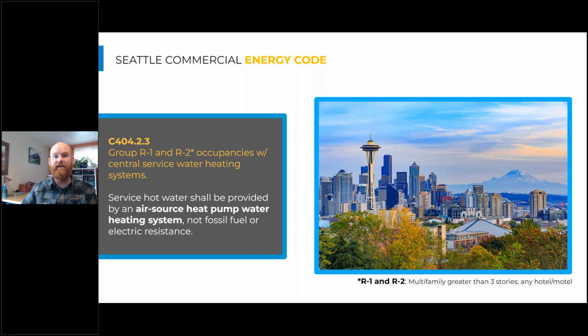Now, it also makes sense in most, if not all, commercial building types: libraries, fire stations, office buildings, restaurants, commercial kitchens. We're still going to see a significant reduction in the annual energy usage when we implement a heat pump water heater. But in multifamily and hotel motel, we take showers, and so there's typically a large hot water demand, and so there's a lot of savings there. And that's one reason that the Energy Code is currently prioritizing making sure that building stock is built with these high efficient heat pump water heating systems first, before it rolls on to all other commercial buildings in the near future.